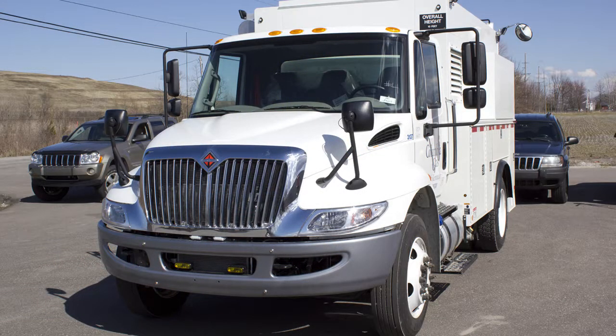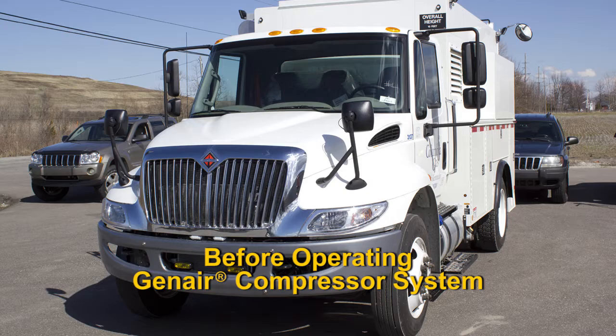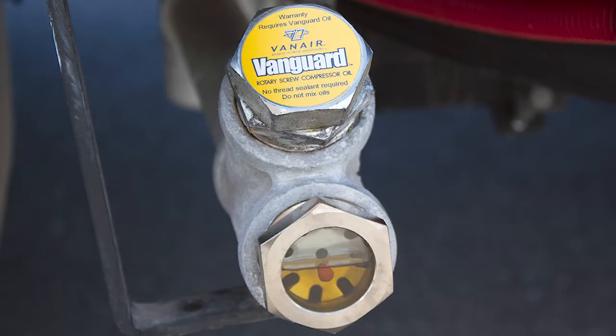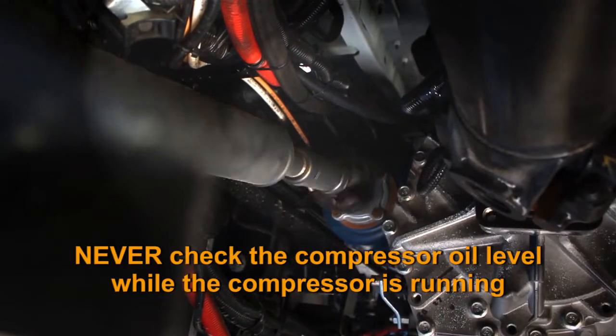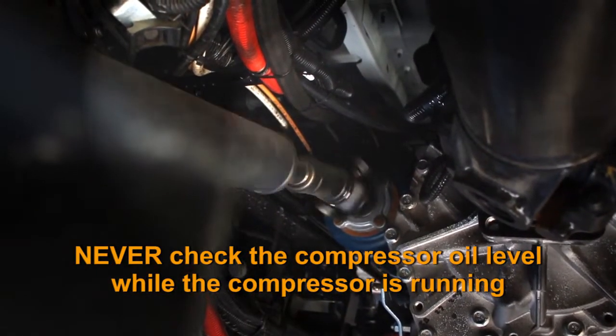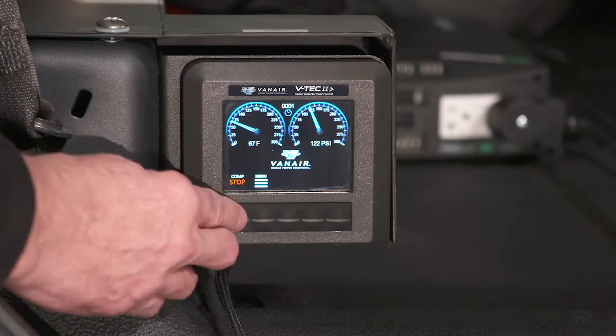There's nothing you'll have to do to initiate this feature, as it will come on automatically when you start the vehicle's engine. With the vehicle safely parked and the engine running, you will need to do the following before operating the system. Check the compressor oil level at the compressor sight glass. The proper oil level will be in the middle of the glass. Never check the compressor oil level when the compressor is running. If the compressor has been running, turn the compressor off and wait for at least 5 minutes before checking the oil level in the sight glass.